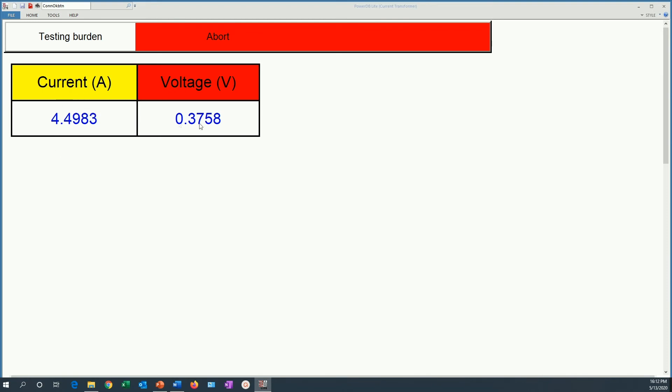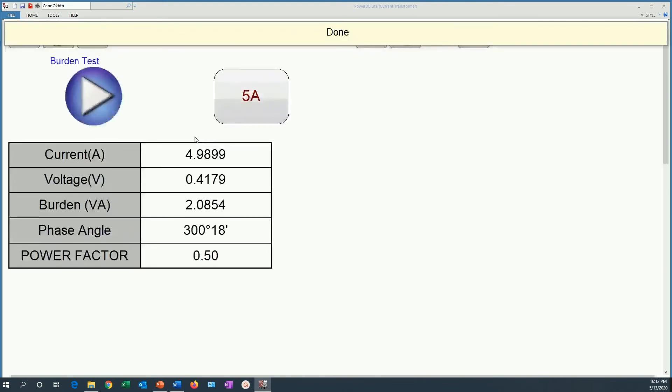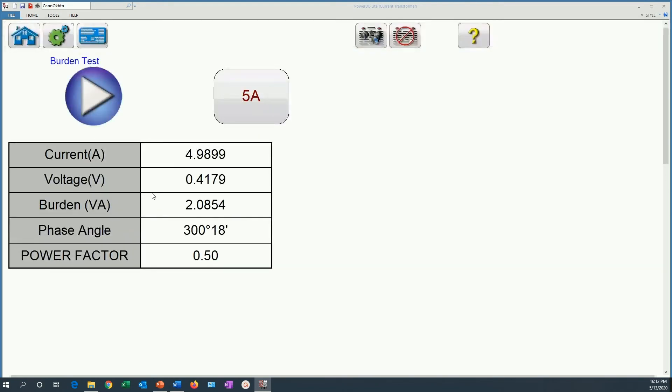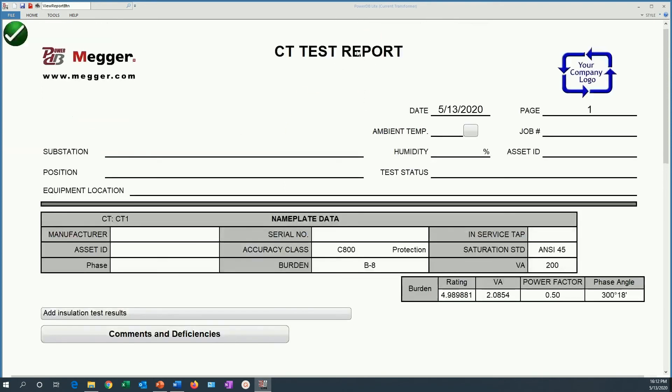It is going to stay there and then it is going to measure the voltage. We are injecting an AC current in order to measure the burden in VA, also the phase angle and the power factor. Once we have seen the results here in this table, we can go ahead and look at the CT test report and look at the burden information on that CT report.